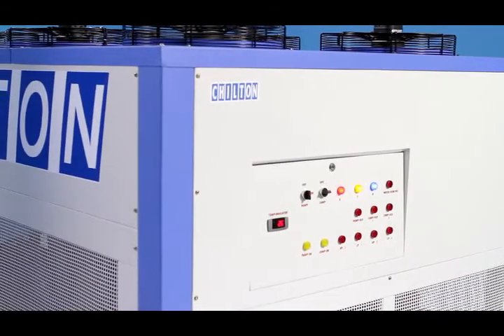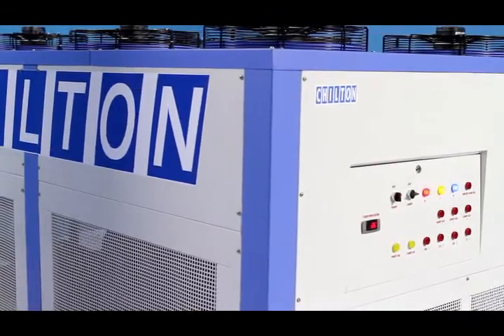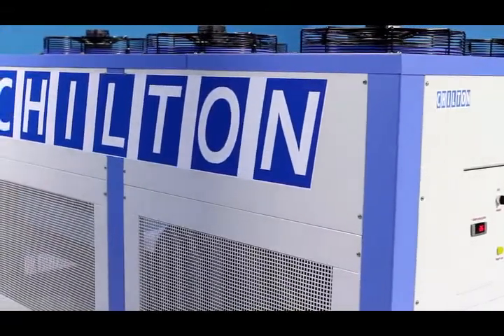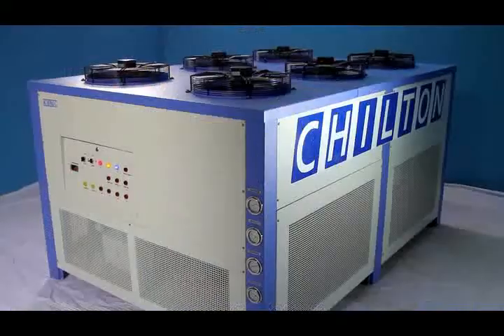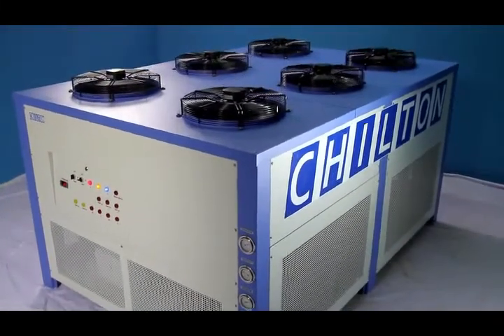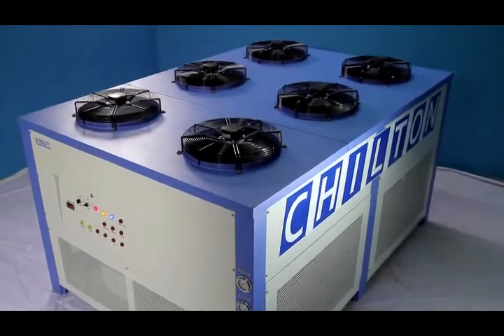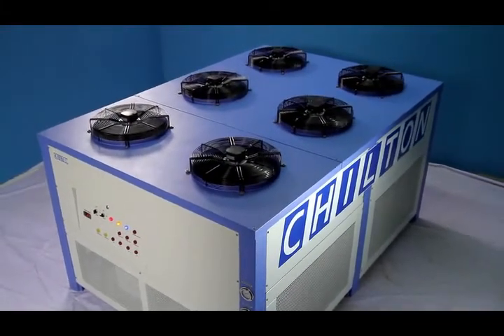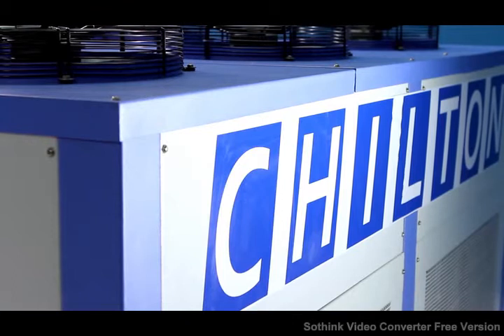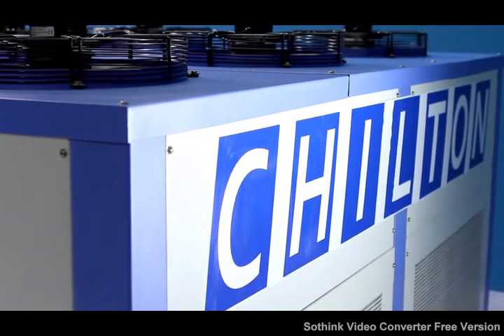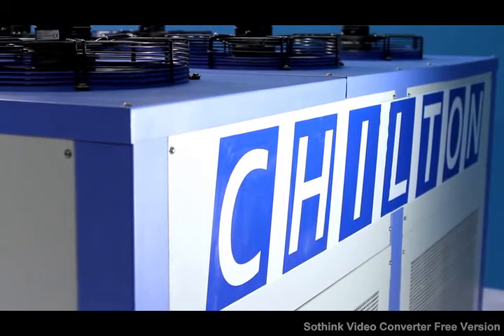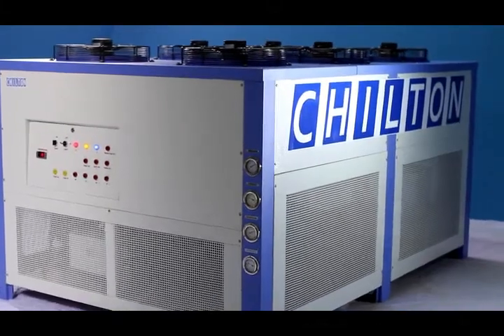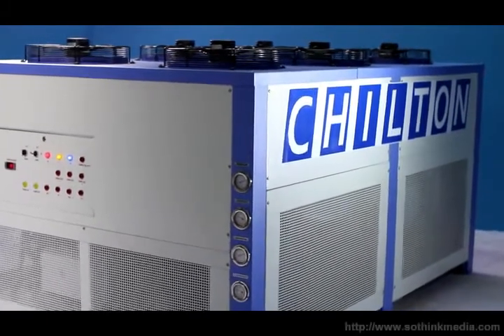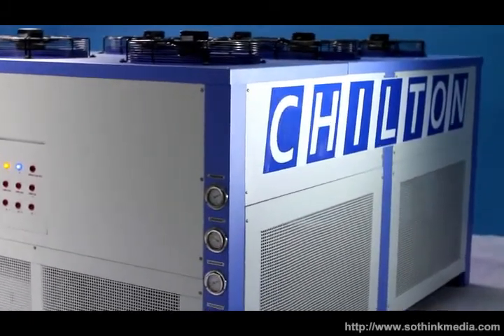Designing the process chiller is very critical since it has to remove the heat generated in the system in a particular time. Otherwise, the temperature in the system will go up and the quality of the products in production will be reduced, and the production rate also comes down. For example, if a room air conditioner cools the room in 5 minutes or 10 minutes, it doesn't matter. But in process chillers, it should not happen. That is why designing a process chiller is very critical.